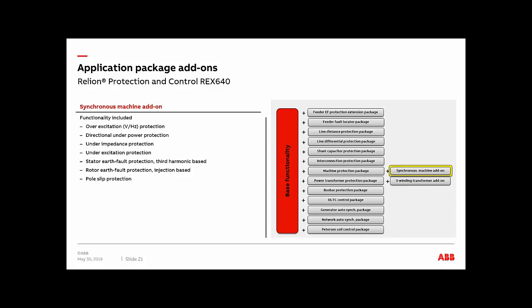Then you've got the rotor earth fault protection, just injection based, and the pole slip protection. 78 out of step protection will cover the pole slip. You can have this one as well in this package.